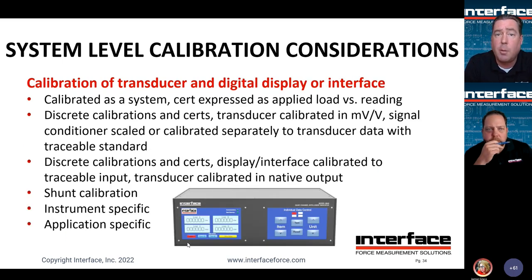Calibration of transducers in combination with the digital display or some other digital interface. Much like the previous option, you can calibrate these as a system or in combination in the rig with the load cell connected to the indicator. And in that case, you'd have a certificate expressed as applied load versus indicated reading. You can also have these calibrated discretely, where the load cell is calibrated in millivolts per volt, and the digital display or indicator is calibrated separately using a simulator, or a traceable standard.